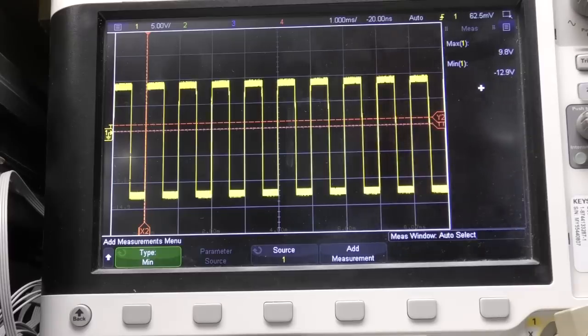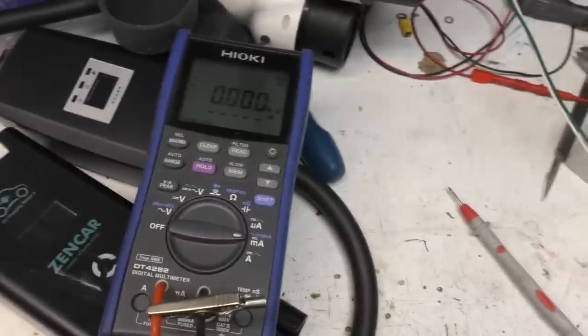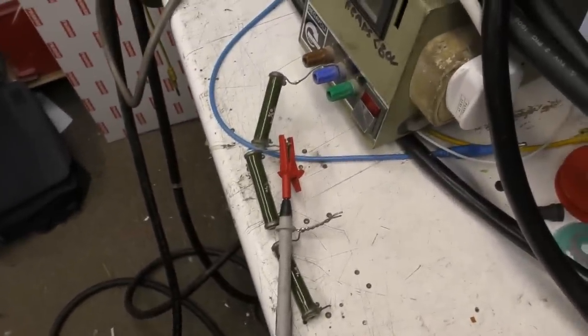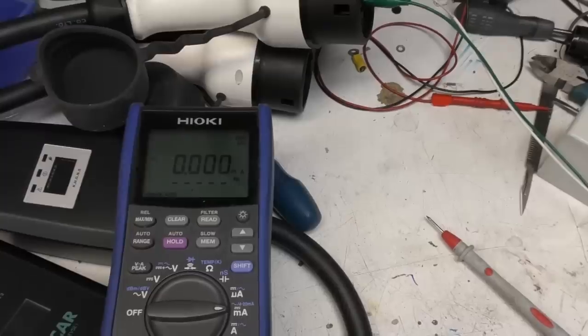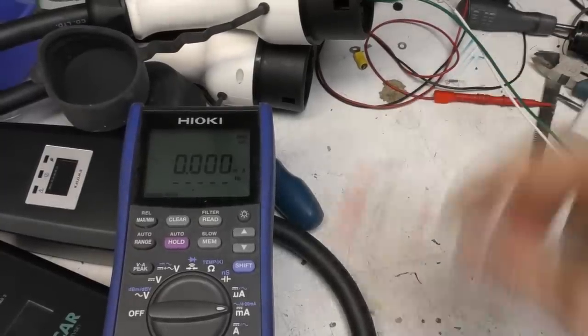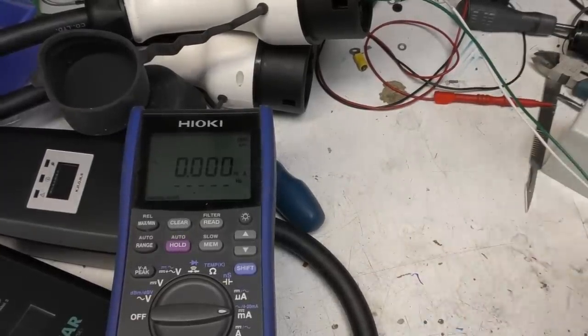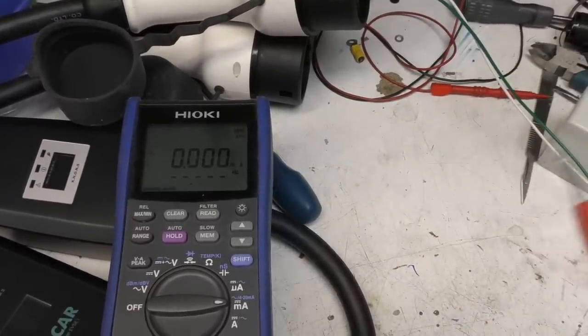It just doesn't seem to make any sense to me. Okay, let's look at the earth leakage performance. The setup I've got here, I've just got some resistors connected to the input neutral via a current meter, and I'm then going to connect that to the output live, so this will produce an imbalance. I'm not doing it to earth just to avoid tripping my incoming earth leakage breaker.